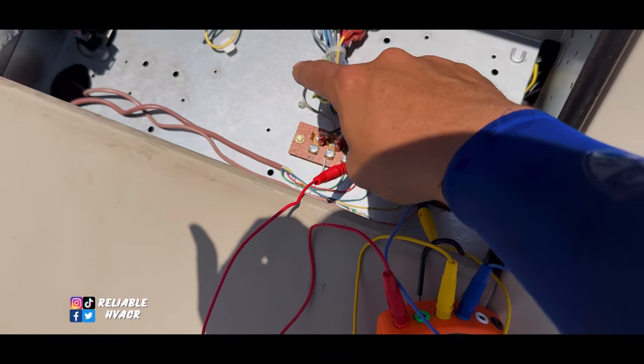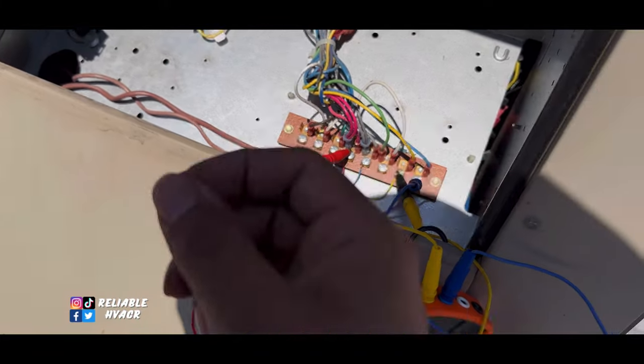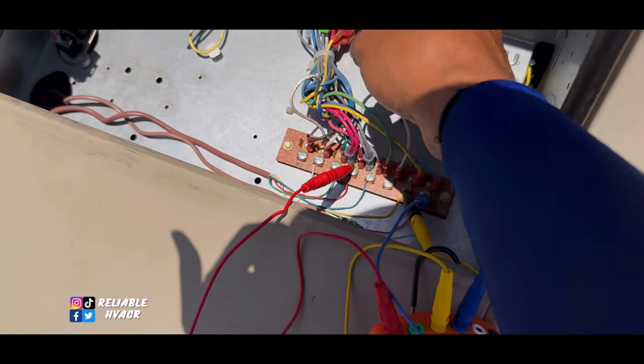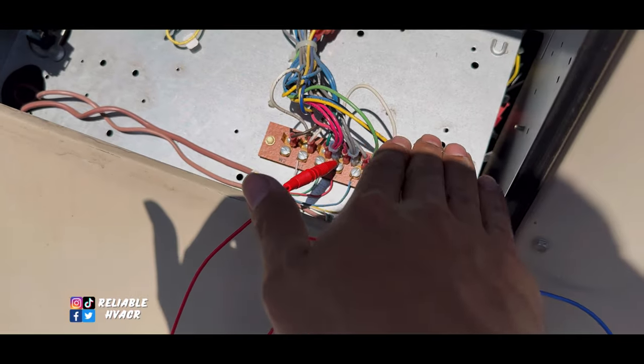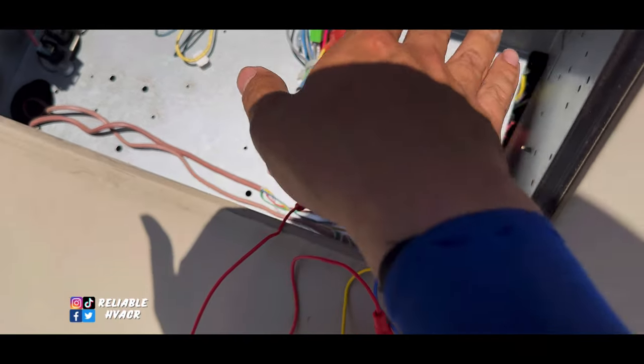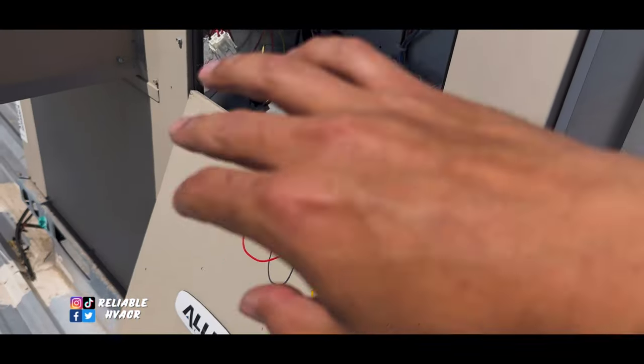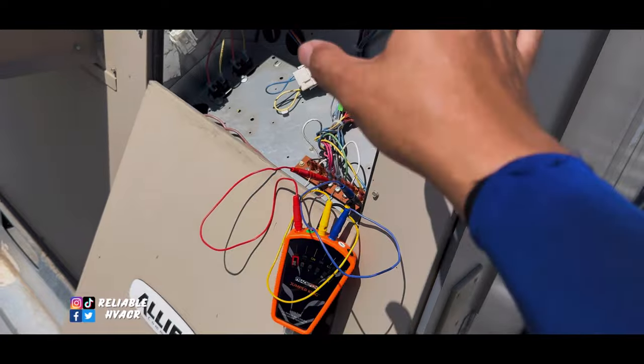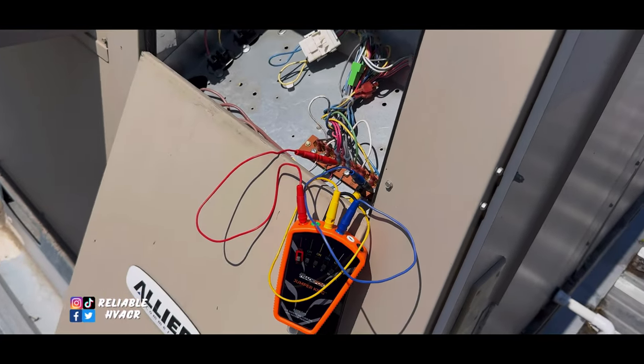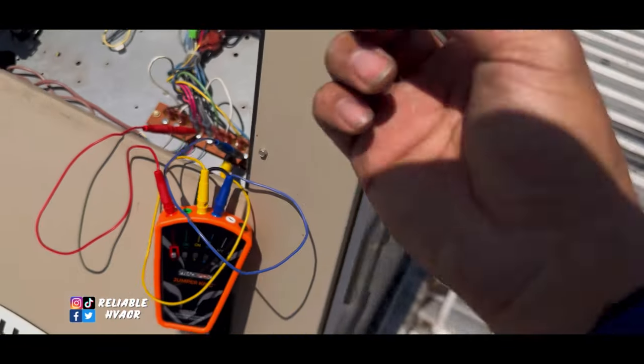And, if you want, I would probably dab a little silicone on the outside if you're worried about it being exposed. But, it leaves the smallest little hole. But, you can, let's say you can't get in here or it's too close to something. You can just find the wire and tap into it and jump it out that way. Anything on the 24-volt side, this works. You know, on an AC unit, you have the, whatever is coming from the board or from the thermostat. Which includes pressure switches and things like that.